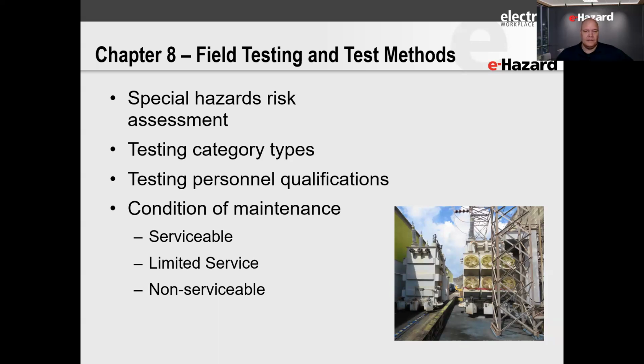Limited service is a little more dialed back. It maybe has some active indications from a PM that show something needs to be fixed, but we don't have to fully replace the entire piece of equipment, because maybe it's just one bearing, a cooling fan, or a space heater that's got some issues. We should hurry up and get that component fixed, but we don't have to fully replace it.